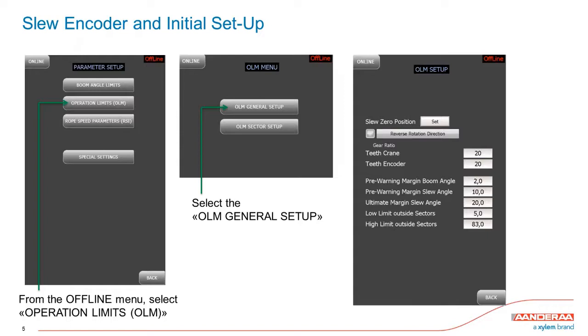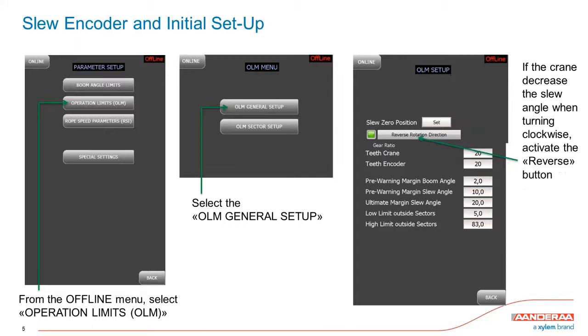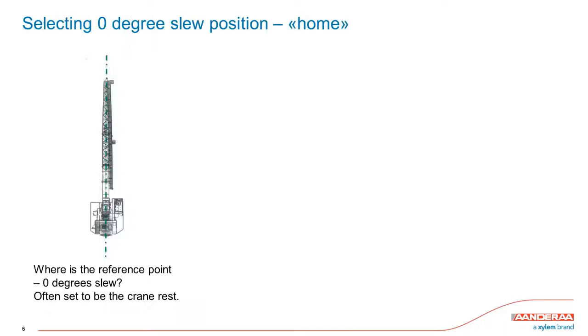Going into the general setup, you will have a setup menu. The first thing you do is actually slew the crane. If I slew the crane clockwise, I would expect the degrees of slew angle to increase. If it decreases instead, something is wrong with the rotation. We don't know if the encoder is installed one way or the other, but if it's logically reversed, we can compensate by clicking on 'Reverse Rotation Direction.' When it goes green, you have logically turned the rotation direction.